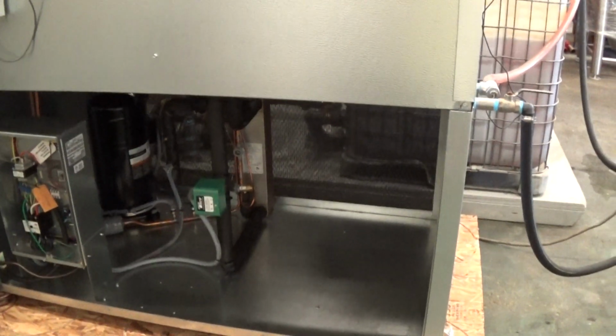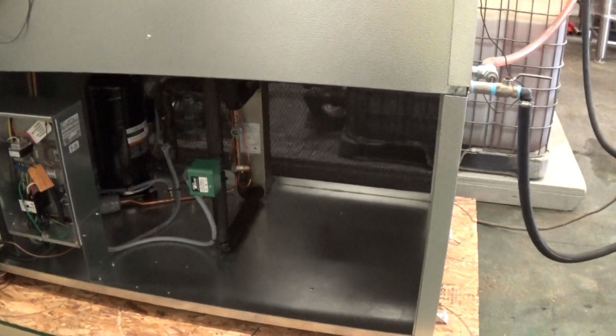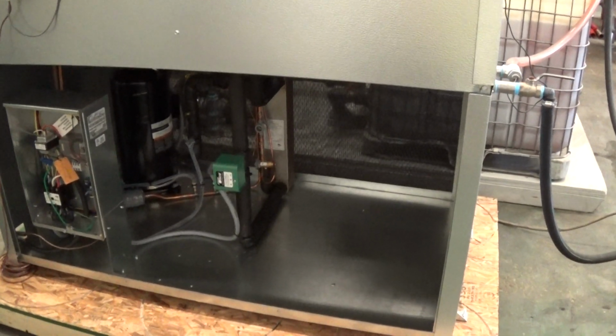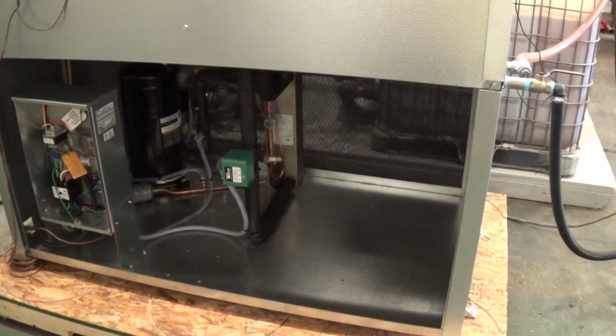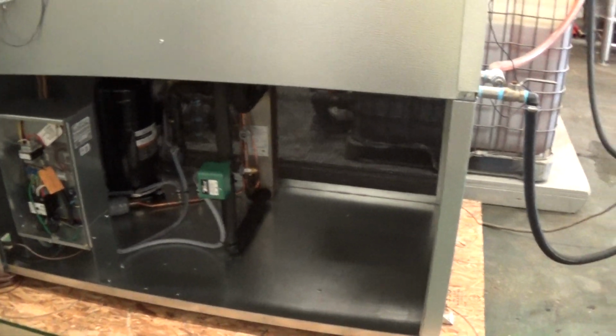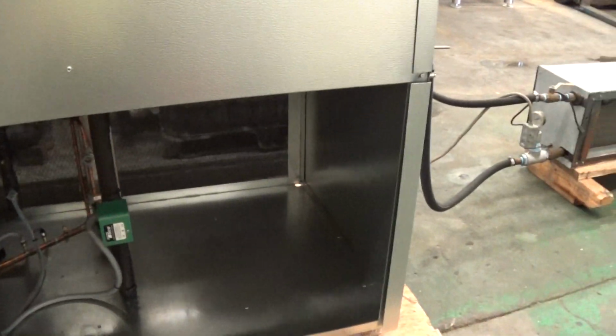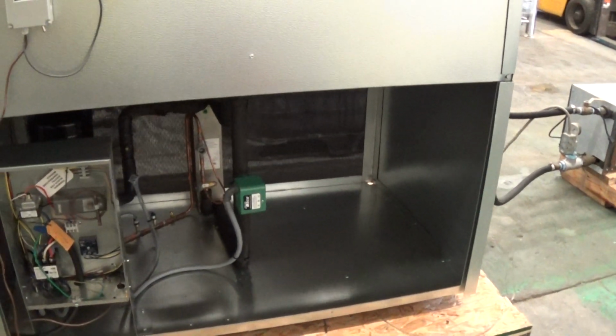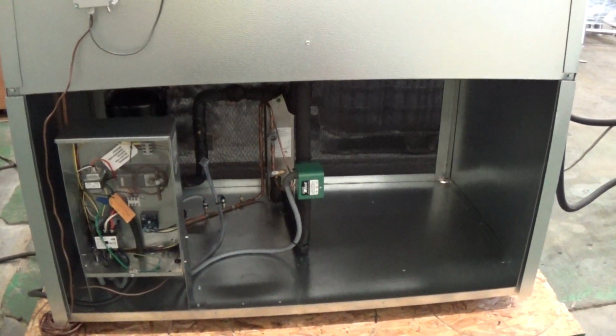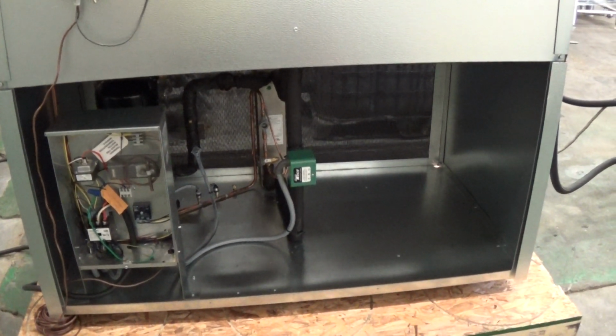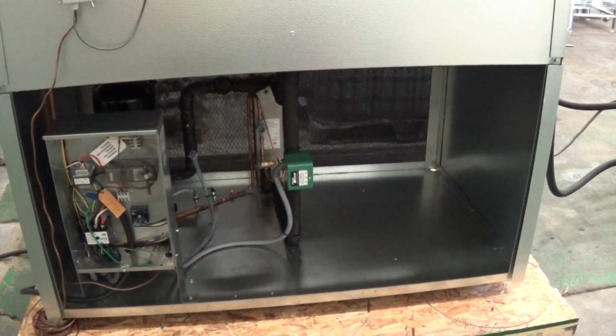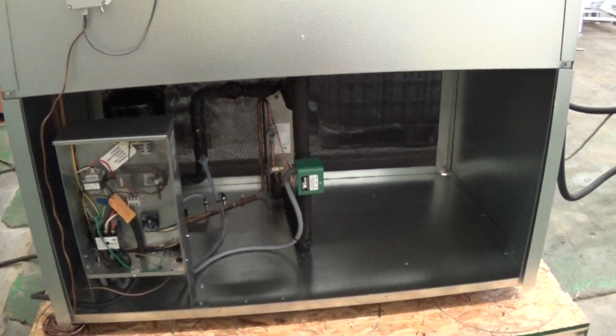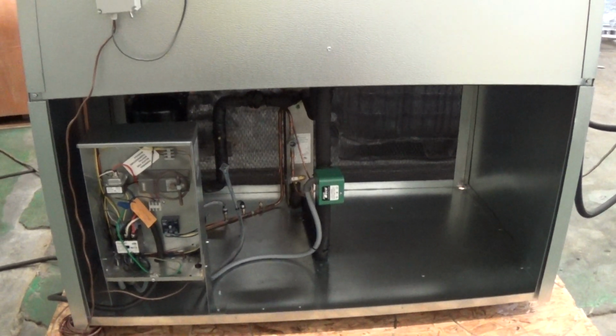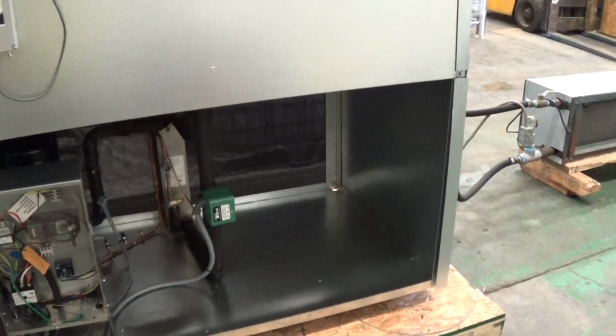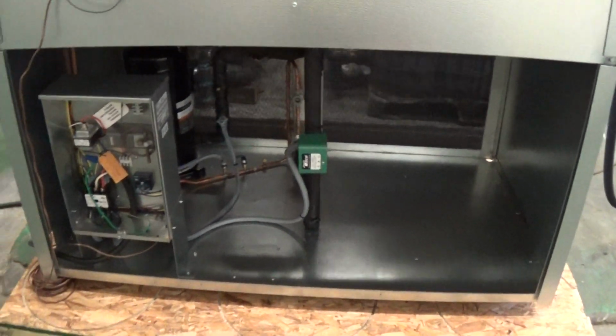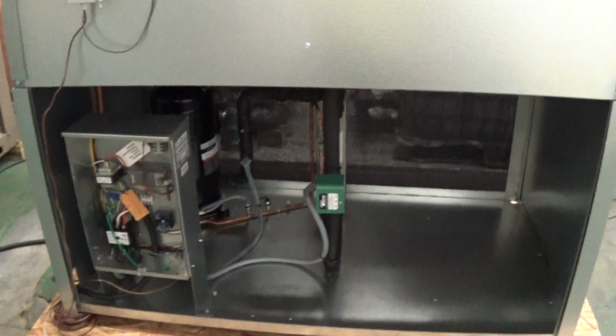Again, this unit's not the packaged version with the pumps or tank. Usually we'll have either 1 or 2 pumps. 2 pumps is ideal, especially if it's going to a process with multiple solenoid valves and heat exchangers out in the factory or brewery or what have you. On a 2-pump system, we'd have 1 pump dedicated just to chill the tank, like an internal loop, and that's fixed at the same flow all the time. Then the secondary pump can be basically at any flow or size needed without affecting the actual cooling performance going through that evaporator.